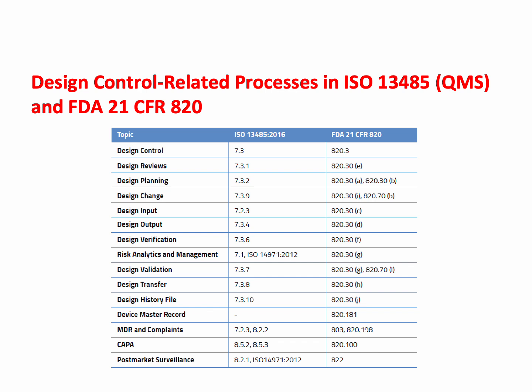What it shows here is that we have regulations like FDA 21 CFR Part 820, or we have international standards like ISO 13485, where they have sections telling us what to do, how to stay in compliance. And now if you want to stay in compliance, you have to have your procedures in writing that are going to always refer to different subsections in those regulations or in the standard. We will need to follow these, and we have to document the fact that we followed the standards and or the regulations whenever applicable.